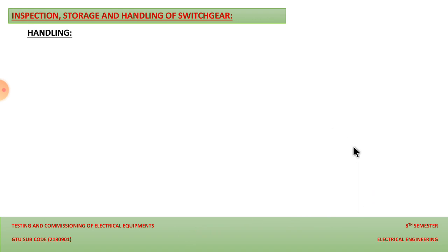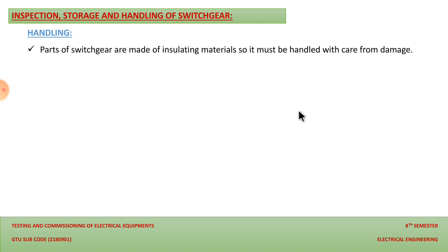So the third point is the handling of the switchgear. How is the handling of the switchgear carried out? Parts of switchgear are made of insulating material, so it must be handled with care. During transit, or during the unloading of the instrument, there might be a chance of insulation damage. If the insulation is damaged, that can harm our switchgear in future, because insulating material provides protection to the switchgear. So we should keep in mind this point while we are unloading the equipment.